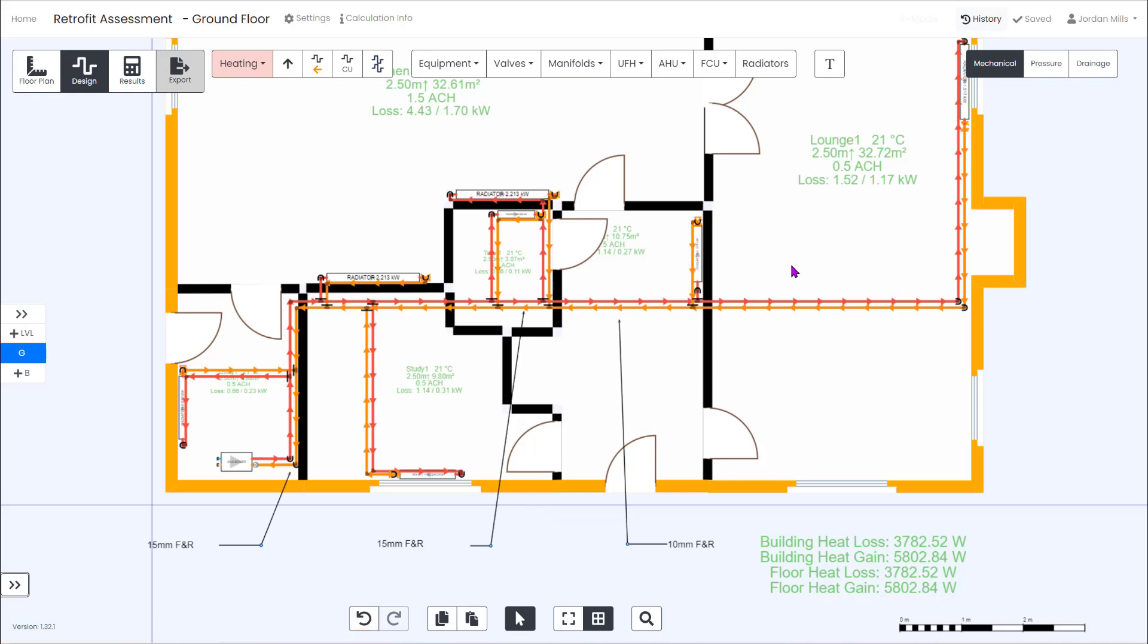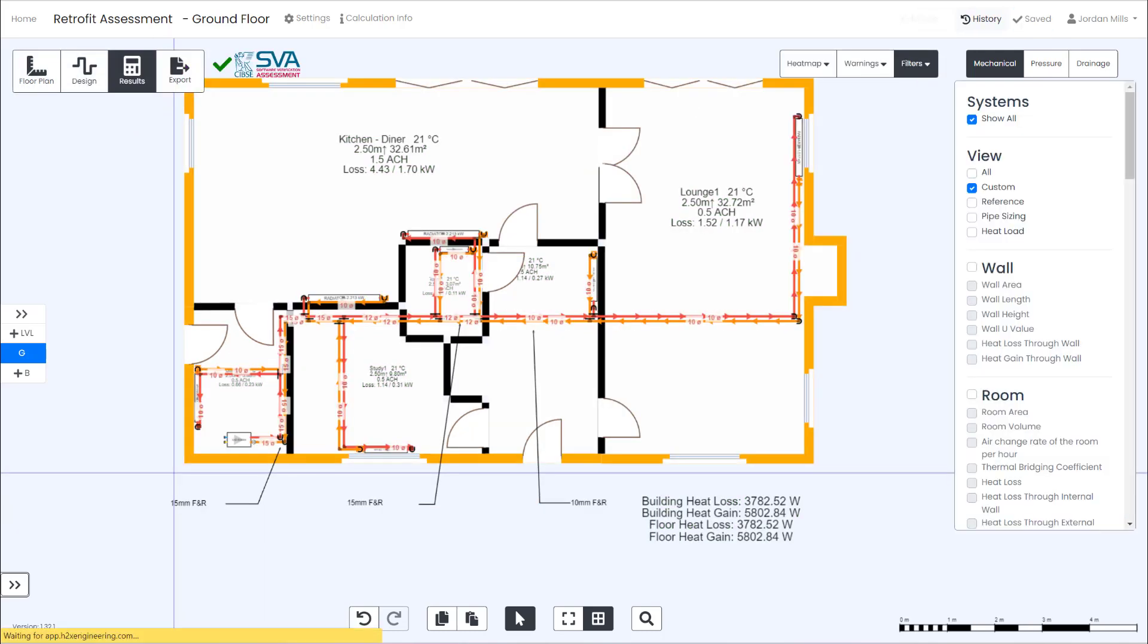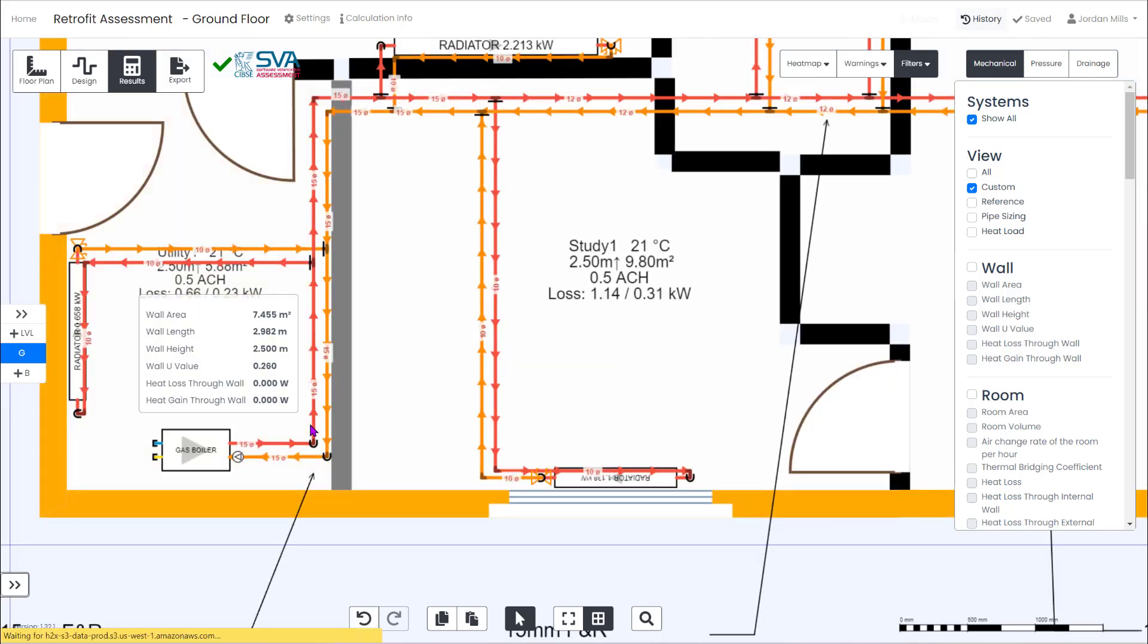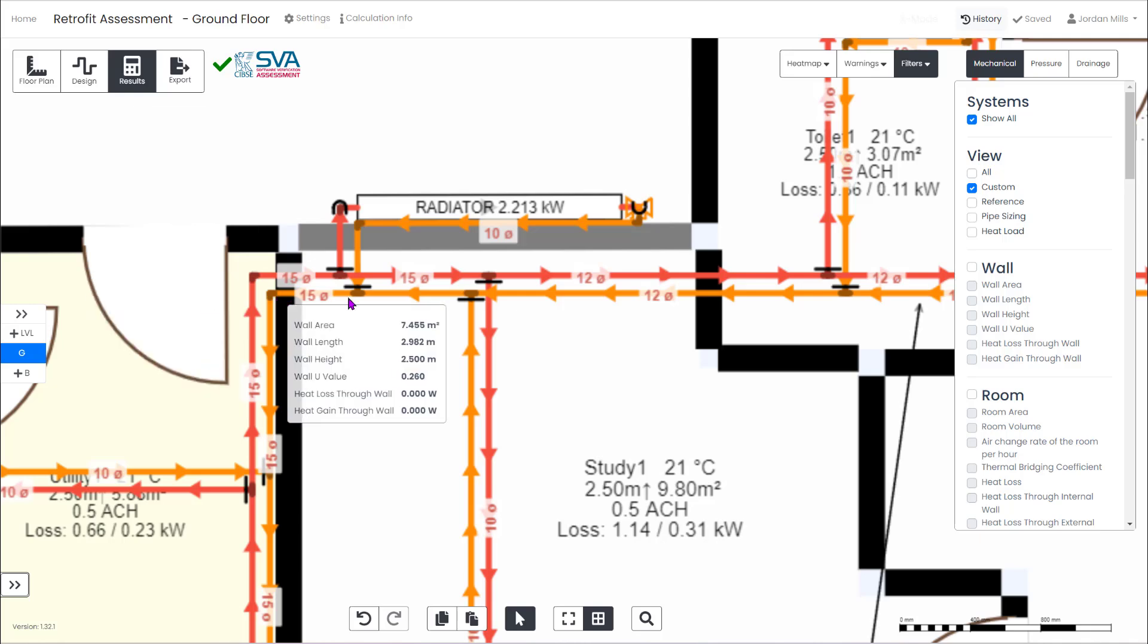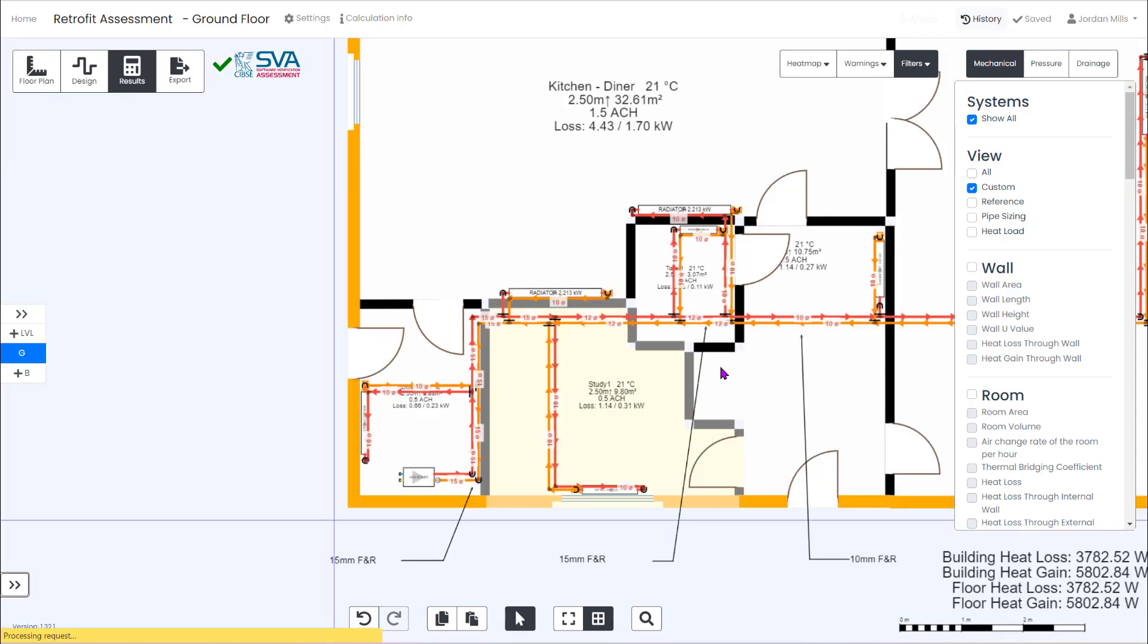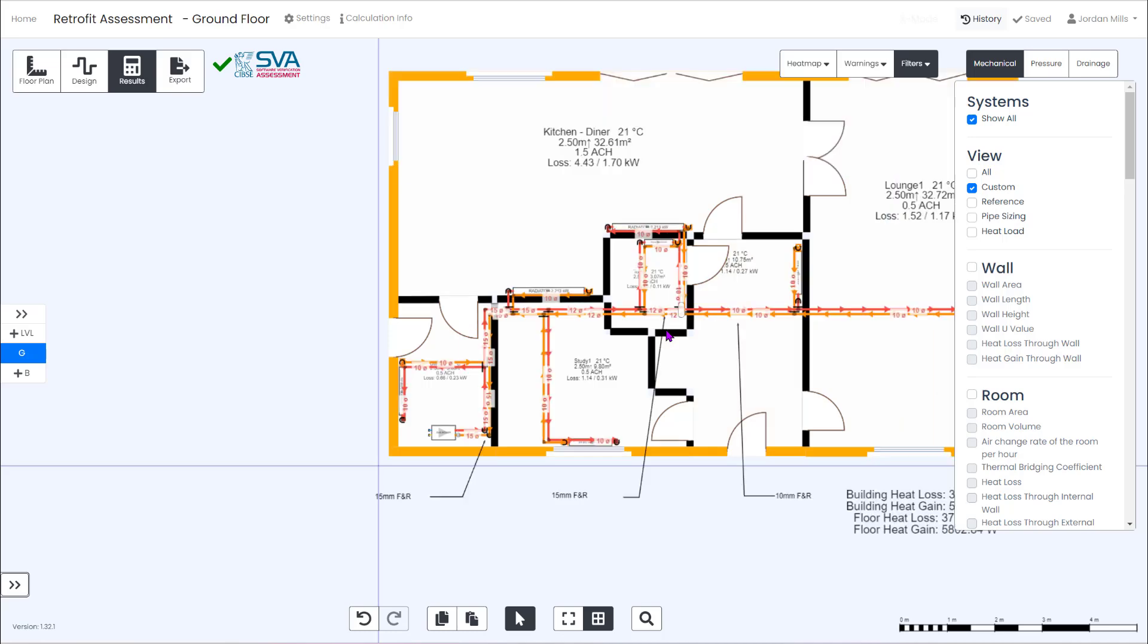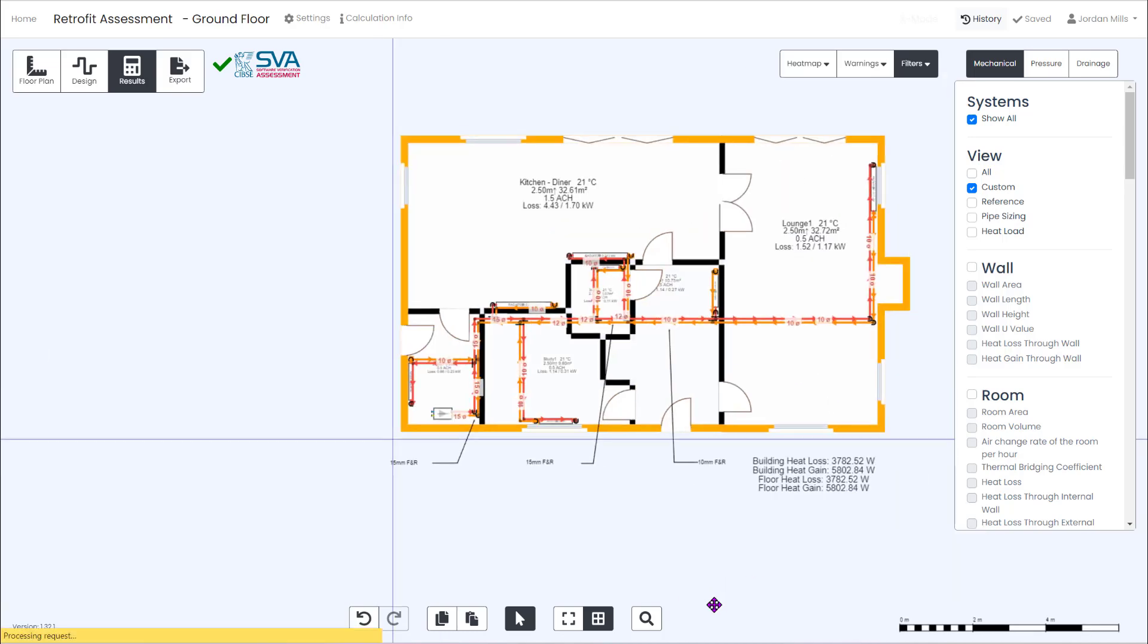Running the results on the existing system we can see a total heat load on the boiler of 10 kilowatts which is quite oversized for the four kilowatts needed to heat the space. You can also see that all of the existing pipe sizes are adequate for the current system. We've got 15 mil from the boiler dropping to 12 mil and 10 mil beyond that so all good at present.